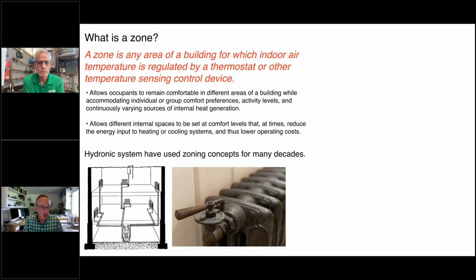The circulation was all done by the buoyancy differences between hot water, which is lighter than cool water. The pipes were sloped. But if you look carefully at some of these radiators, you're going to see a valve like this, some type of a manually adjusted valve that would simply change the flow rate or allow the flow to be completely stopped going through an individual radiator. So that's, again, going back literally over a century.